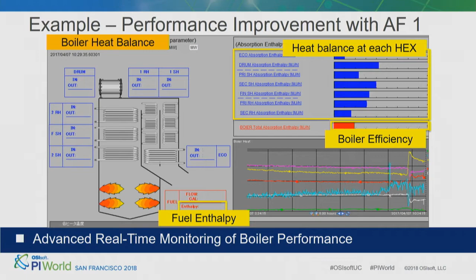Here is an example where we tried to optimize spray water injection control of the HRSG superheater attemperator. Normally, we use the temperature of superheated steam for spray water valve control, but we experienced troubles like delay in control caused by flow characteristic deviation between design specifications and actual conditions.